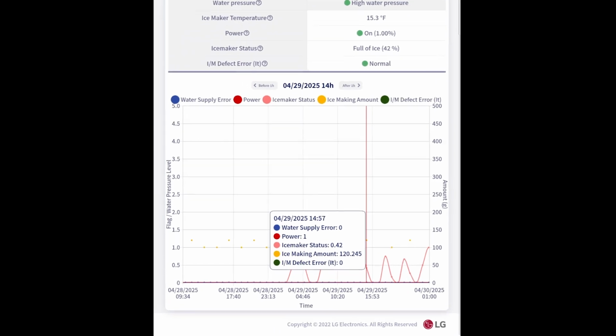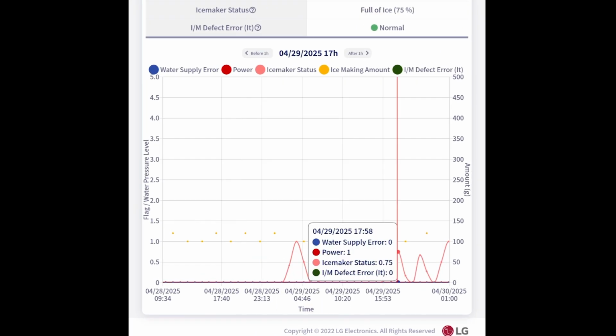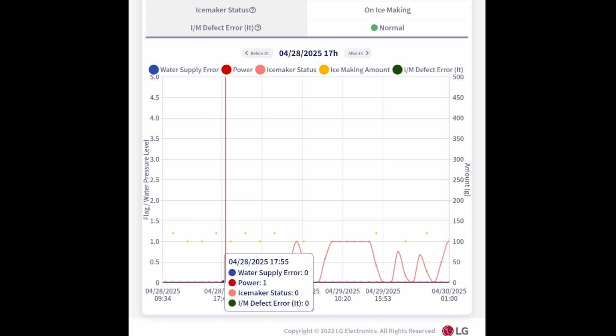Another thing I want you to notice is wherever you click out on the chart, the box pops up and gives us some information. So right there, water supply, or if there had been any water supply issues, that would be a number 1. There would also be a blue bar on the graph. Power is number 1. So 1 means that it is powered on. If it were 0, the ice maker would be powered off. Ice maker status, that's how full the bin is. And since it's in ice making mode right there, it's not giving us a status at this time. And then ice maker defect error, IT. So if there was an IT error code, that would be number 1. You would see a green bar on the graph if it was given an ice maker error code.